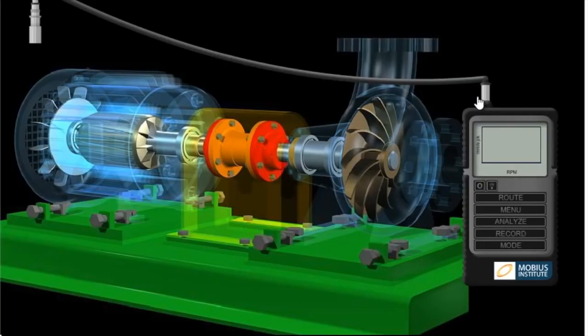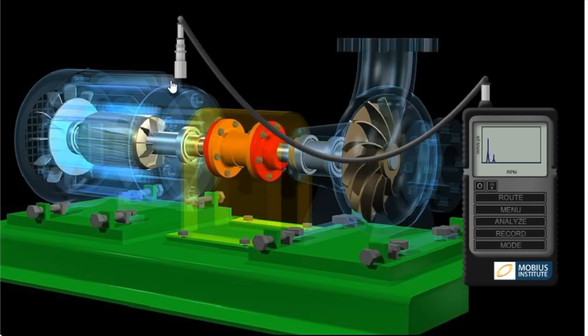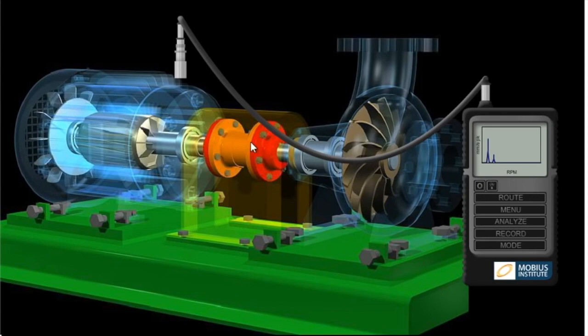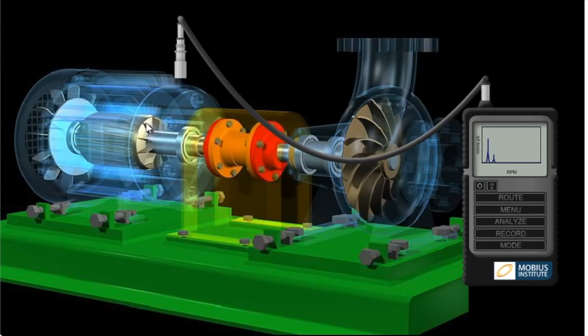The way we do this is, as you've just seen, we can put the vibration sensor up there on the bearing and all the vibration is transmitted through the machine itself up to that point. The sensor has to be mounted properly. That is very important so that all those high and low frequencies get up into that sensor.